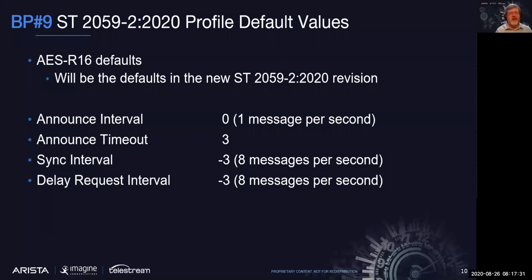The key values here are an announce interval of 0, a timeout of 3, a sync interval of -3, or 8 messages per second, and a delay request interval of -3, or 8 messages per second. A lot of thought has gone in by various experts to come up with these values. They've been tested at various interops and the JT-NM Tested program, and widely deployed in the field. So unless you have a really, really good reason, you should stick to these defaults—they work very well.